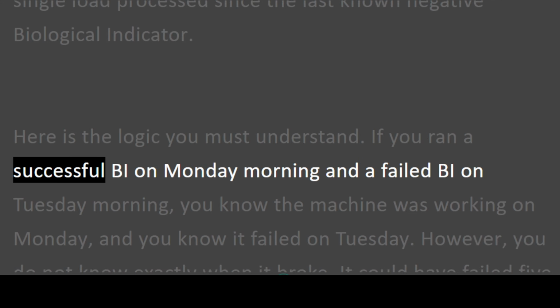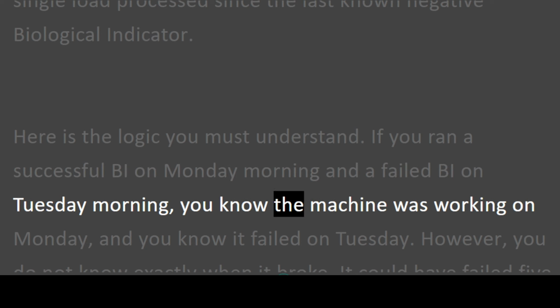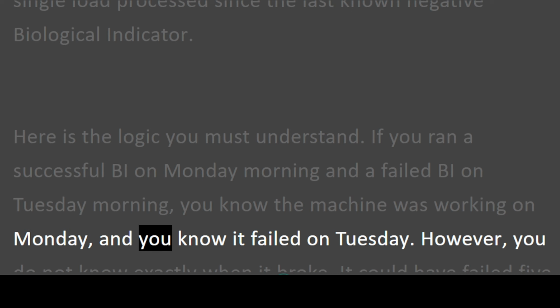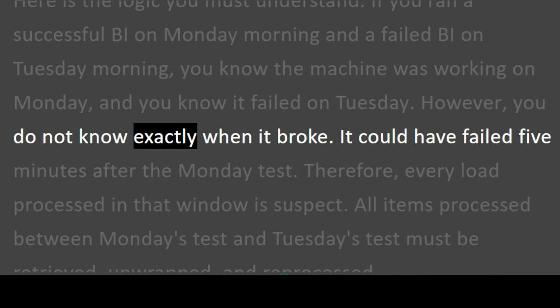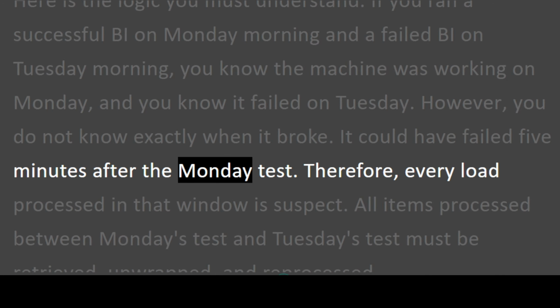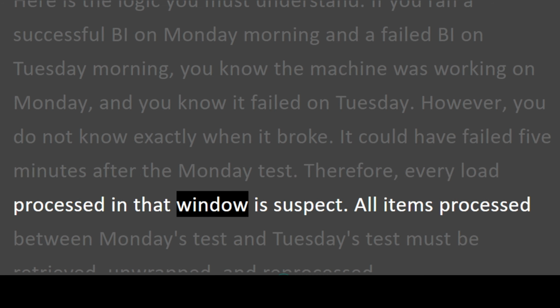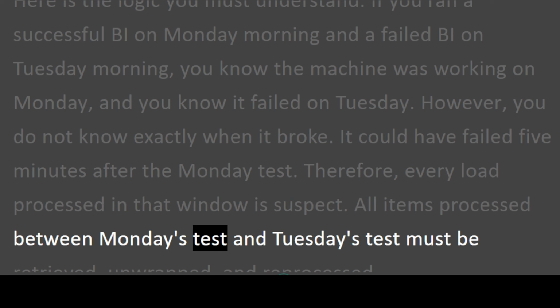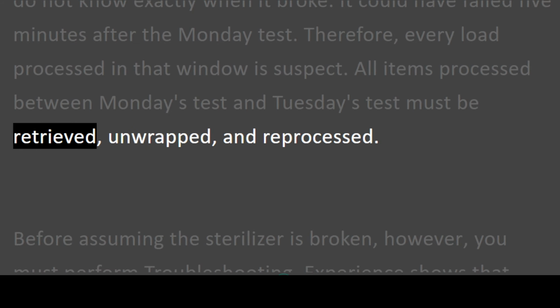If you ran a successful BI on Monday morning and a failed BI on Tuesday morning, you know the machine was working on Monday, and you know it failed on Tuesday. However, you do not know exactly when it broke. It could have failed 5 minutes after the Monday test. Therefore, every load processed in that window is suspect. All items processed between Monday's test and Tuesday's test must be retrieved, unwrapped, and reprocessed.